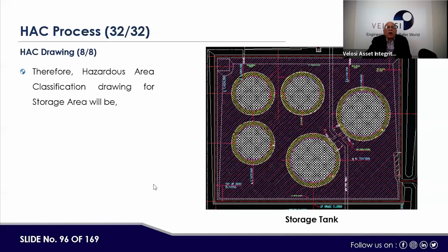Okay, there's a question from Willie Santinta. Are MSDS still used? Are they not replaced by SDS in the year 2000? Yes, MSDS is old terminology, which stands for material safety data sheets, and now it is safety data sheets. You can use either one, because we basically need information regarding the process, with reference to the diamond, the four categories, and that is used basically for the HAC classification, and number two, for the data sheet of the electrical and instrumentation in the process area.